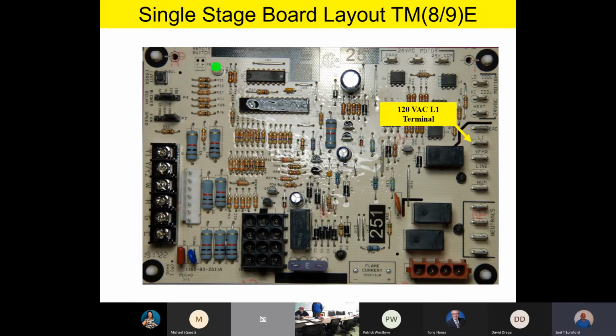Right below L1, we have XFMR. That's our primary high voltage lead to our transformer. Right below that, it says line. Now this is interesting. The line is actually the power going to the ECM motor all the time. So L1 is where the power comes in, but where it says line, that's what's powering the ECM motor up all the time whenever we have power to the furnace.